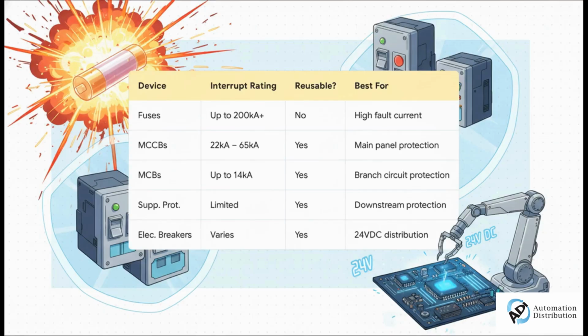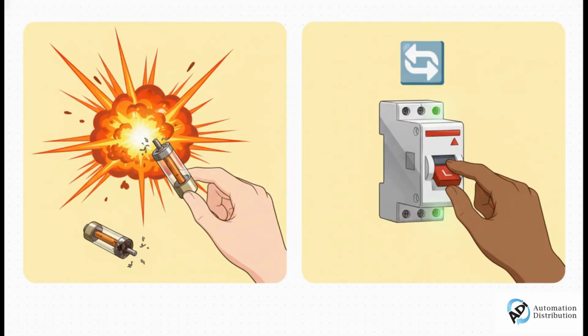The key difference, of course, is that they're reusable. And way down at the other end, for your really sensitive 24-volt DC stuff, you have electronic circuit breakers, which give you smart, precise protection. And this brings us to that age-old decision you're gonna have to make: fuses or breakers. It's really a classic trade-off. Fuses are cheap and give you amazing protection against those massive faults, but when they blow, you gotta replace them. Breakers, on the other hand, cost more up front, but you can just reset them with the flip of a switch, getting you back up and running in seconds, a lot of times without ever opening the panel door.